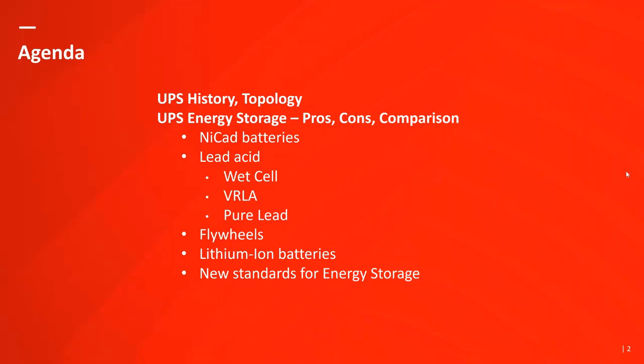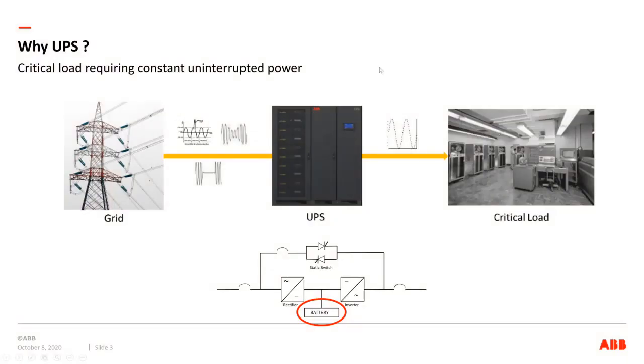Next slide, please. That's about why UPS and what a UPS is. Basically, a UPS is a filter. It takes power from the utility, and in most data centers there will also be an emergency power supply, a generator. If utility power fails, the generator will kick in and start supplying power to the UPS. The UPS will filter that power no matter where it's coming from and supply clean AC, 480 or 208 volts, to a critical load. UPS is uninterruptible power supply, and what actually makes it uninterruptible is the little thing I circled in red at the bottom of this slide, the battery, which is the energy storage.